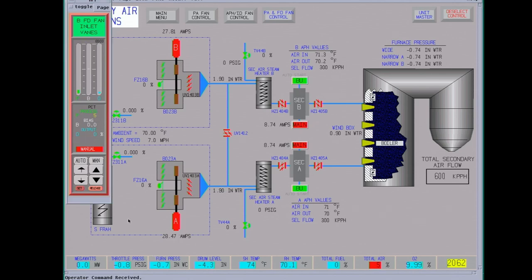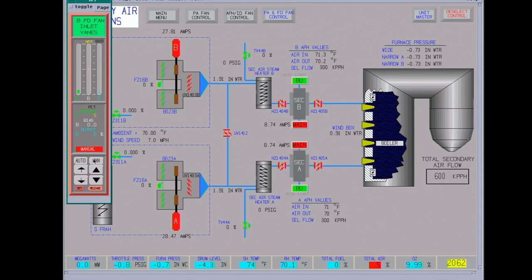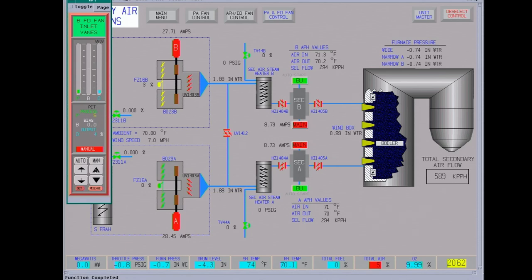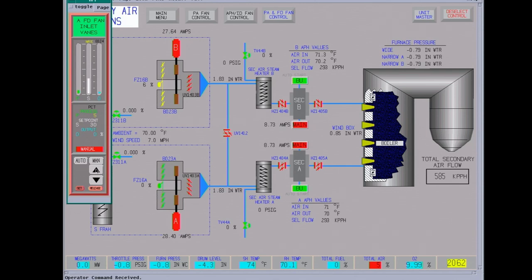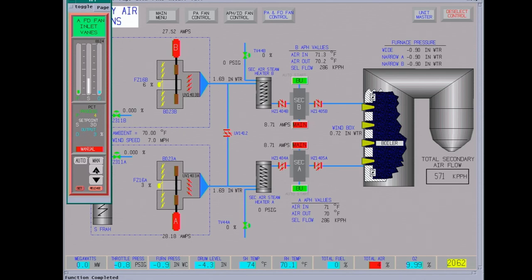Usually you want to take a few percent on each fan, and hopefully the ID fan control will catch it. Basically we want our air flow up above 30% for our purge permissive. Pretty much all furnaces have purge permissives. The purpose is to get rid of any combustible gases out of the furnace so you don't have an explosion.